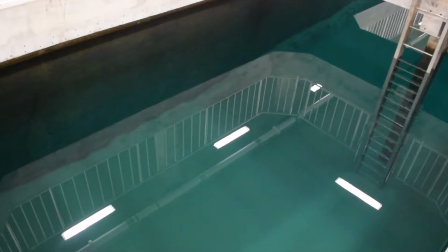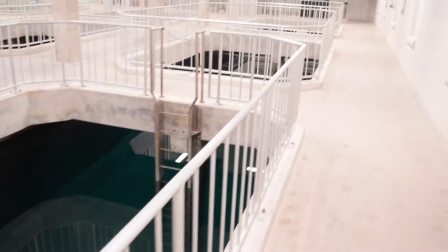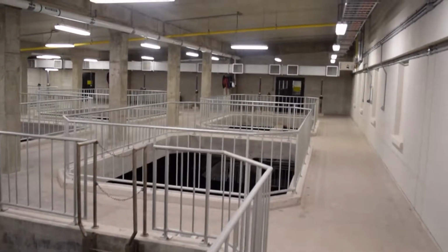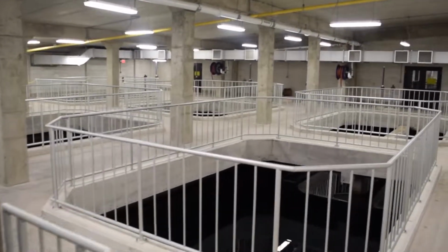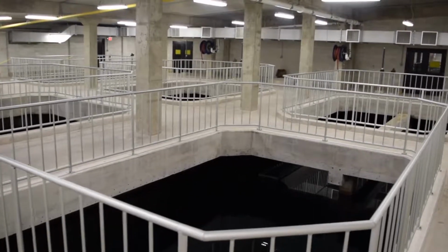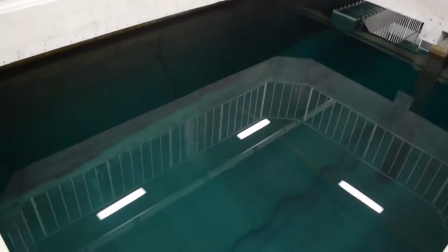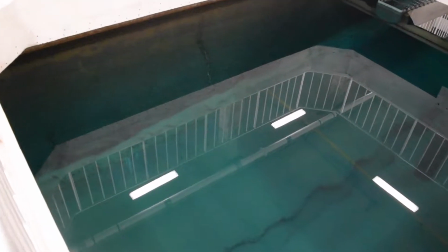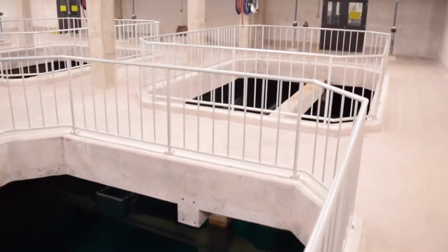Sedimentation is a process of removing settleable materials. This is done by decreasing the flow velocity in the settling basins to lessen the ability of water to hold particles in suspension. The main function of this basin is to remove as much of the suspended particles as possible to reduce the risk of clogging the filters and increasing the runtime between backwashes.